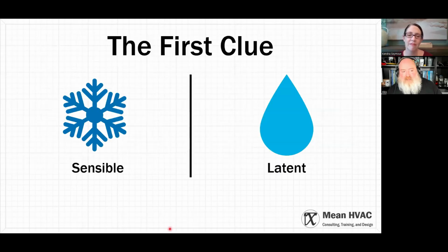So the first clue we should have that this stuff is not the right stuff, AHRI, is they don't split it up into sensible and latent. You have to pay attention to humidity and temperature control separately. Make sure you're aware of both. If you lump them together, you're going to get burned.